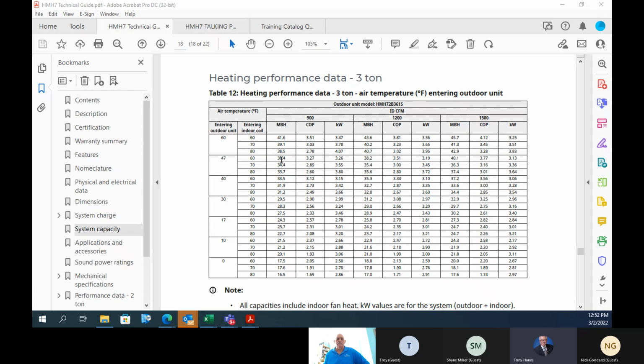But what we look at up north here is the capacity as we start to get down into colder temperatures. You can see that the unit is rated here, not only at the ARI ratings, it's rated from 60 degrees down to 0 degrees. I just took a look at this 3-ton unit, and if you look at the median airflow, and to Joel's point, if you have a 3-ton unit, you really want to shoot for 400 CFM a ton. So 1200 CFM on this is what I looked at.